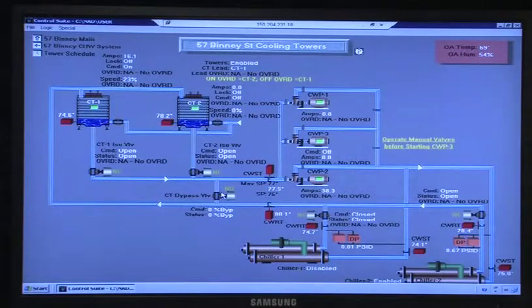so cold out that you can return the water back, I believe it just bypasses the towers here and goes back up through and does this. Normally closed. Yeah, doesn't it? It tries to maintain like 77-degree condenser water. Is that normally closed, the bypass? I'd have to see what I have it. I don't know if it's normally open or normally closed, but normally it's going to try to maintain 75 degrees.